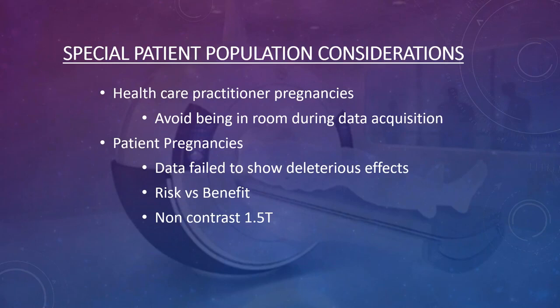It doesn't matter what trimester of pregnancy — many years ago we avoided having first-trimester staff near the magnet, but that restriction has been largely lifted. The ACR only recommends that the pregnant healthcare worker not enter the magnet room while it is imaging, simply because there is no research available, since testing pregnant individuals for safety effects would be unethical.